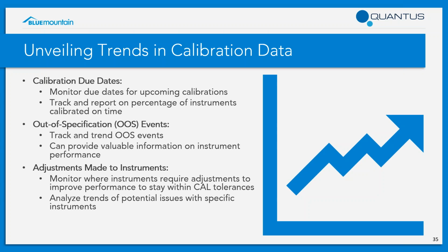As you see out of tolerance or out of specification events, you're going to keep track of those related to measurements taken with calibrated instruments. Investigations on these can help determine whether they were a calibration issue and what appropriate action to take, and how often something is failing, whether you want to reduce that interval or not.